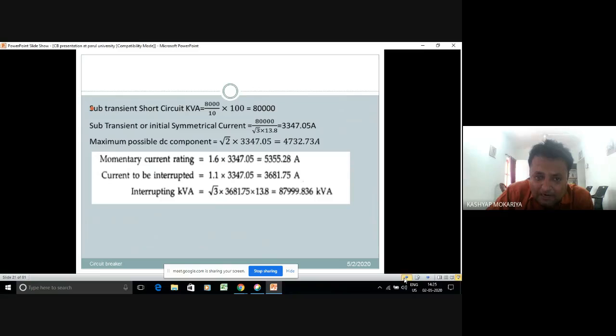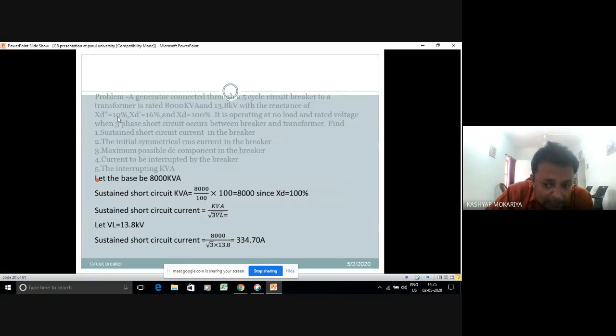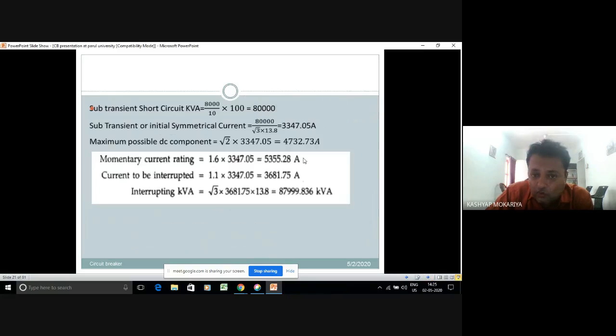Now I can see the subtransient short circuit kVA is equal to 8000 by 10. I'll go to the back slide. What is 10? 10 is your X_d''. I showed that the initial phase the breaker has to take care of is this subtransient period, and this period is very lethal because the breaker has to go through it. So that value comes multiplied by 100. That value comes somewhere near 80,000. So the subtransient or initial symmetrical current.